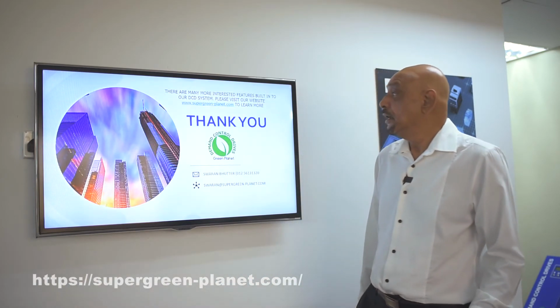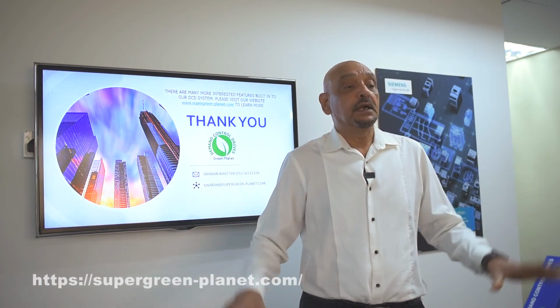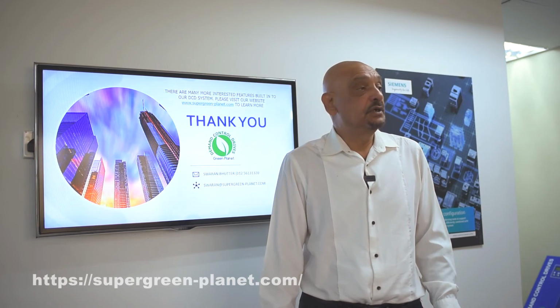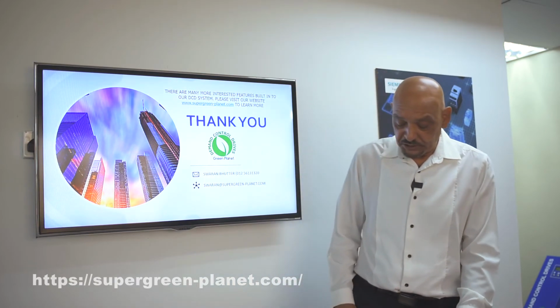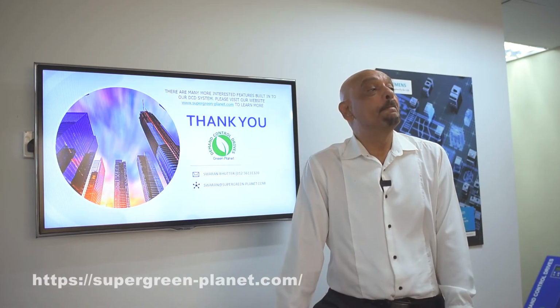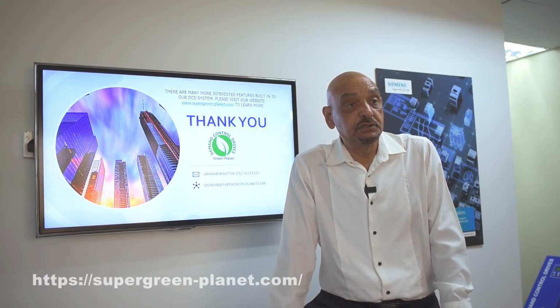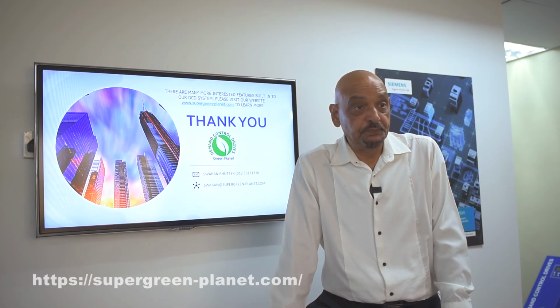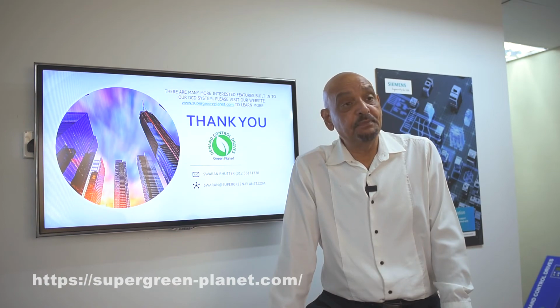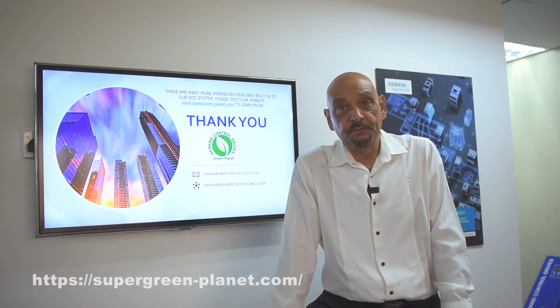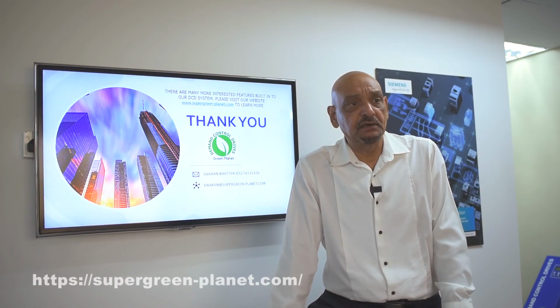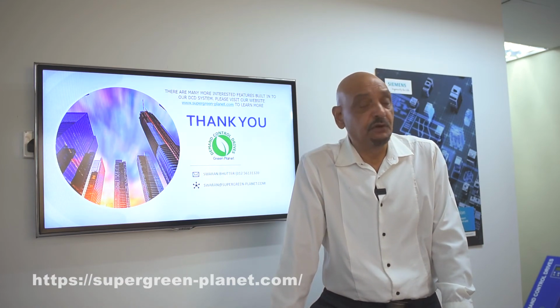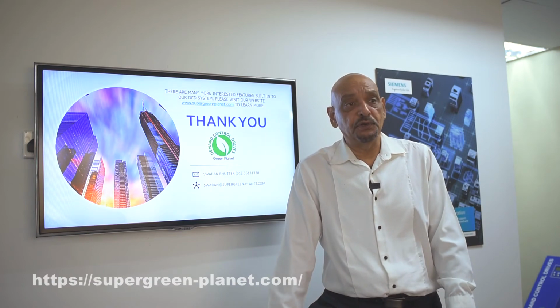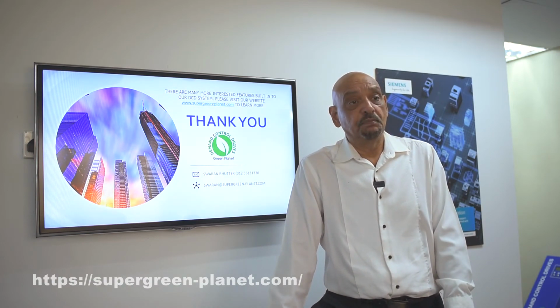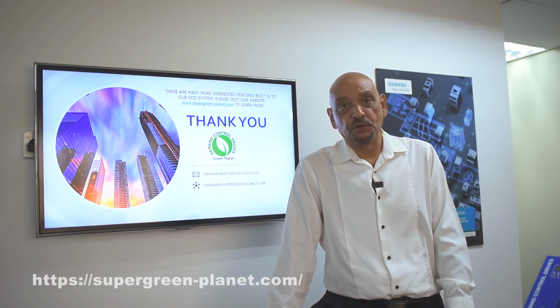Now, what else we have not mentioned is your water pumps. As far as your water pumps are concerned, you have a tremendous amount of potential to save energy, right? Now, a water pump is not a variable demand, a water pump is a fixed demand. We will do some mathematical calculation as to what the exact pressure required is, right? If your motor's water pumps are uncontrolled, you may use valves to control the flow of water.